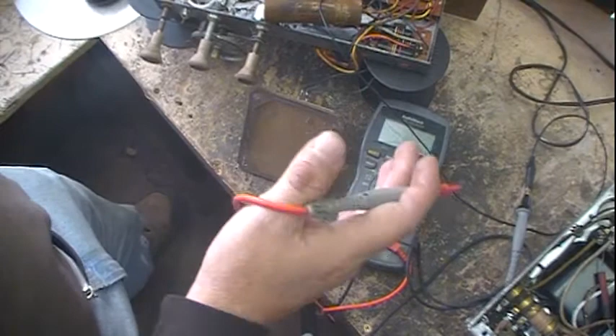If you do have a meter that has ranges on it, then always, when in doubt, or even when not in doubt, set it to the highest range on voltage and then work your way down. Each time you click through and change a range, pull your lead back away so you're not reading anything across it, then switch down and check again to see if you get a reading. Until you get a decent reading, you can keep going down.